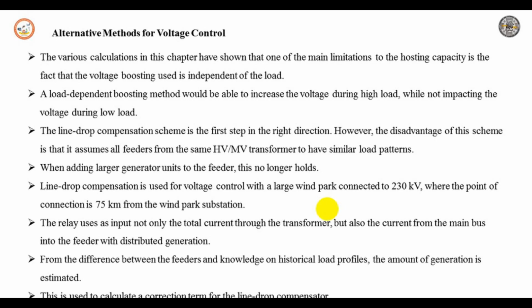The relay uses as input not only the total current through the transformer but also the current from the main bus into the feeder with the distributed generation. From the difference between the feeders and the knowledge of the historical load profile, the amount of generation is estimated. This is used to calculate a correction term for the line drop compensator. A successful field trial of the relay was done in an 11 kV network with 13 feeders and 5 megawatts of wind power connected to one of the feeders.